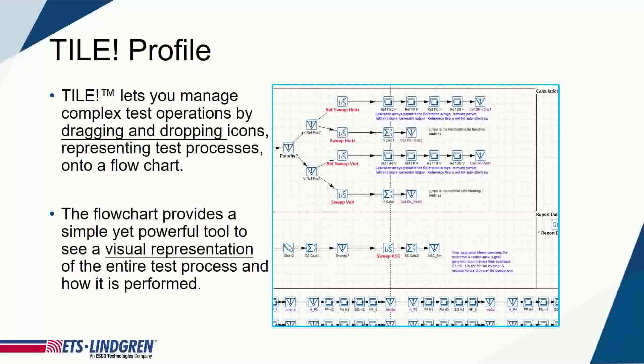The flowchart provides a simple and powerful tool to see a visual representation of what's going on. When an action is running, it actually has a blue halo around it. When it completes successfully, it illuminates in green, and if there's some kind of failure, it turns red. So there are very easy cues to see where you are in the test flow while a test is running.